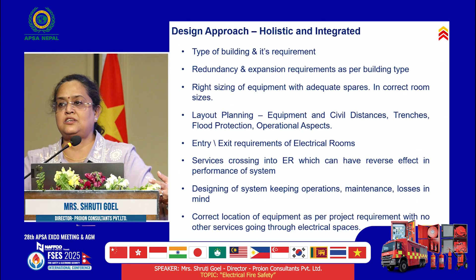That is the question you should ask yourself whenever you are designing such spaces. Size it rightly, don't oversize or undersize it. Provide room sizes according to the equipment you have sized. Do not assume that if in future you need to increase the substation size or DG size, you should not require changing the room size.